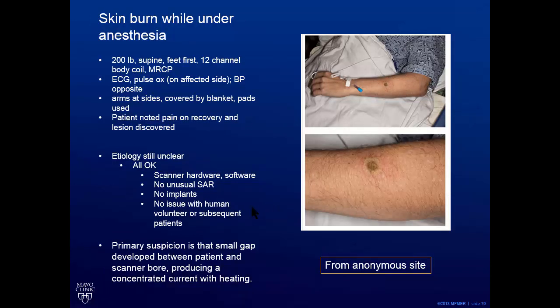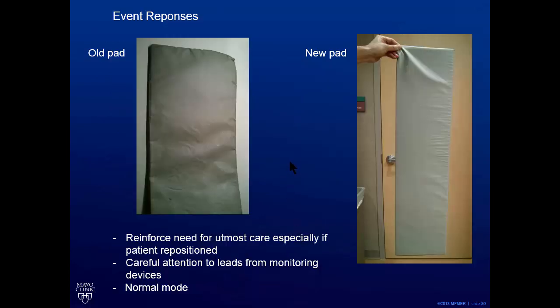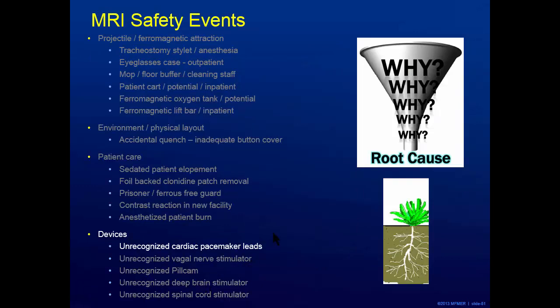A burn occurred at an anonymous site. The patient was under anesthesia and the lesion wasn't discovered until after the exam. Everything checked out on the magnet, and the only suspected cause is a small gap between the patient and the scanner bore that concentrated the current against the bore, causing the burn. The pads have since been replaced, and it reinforces the need to be especially careful when patients are repositioned in the scanner under anesthesia, and to be very careful about looping of leads with monitoring devices and to scan in normal mode.